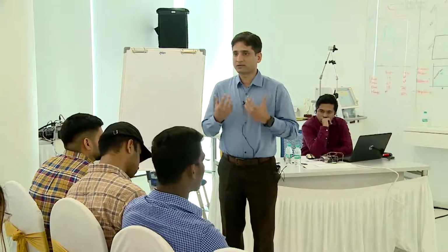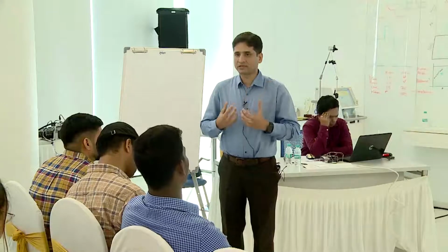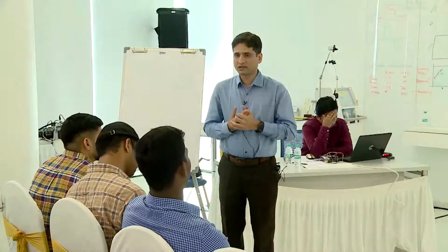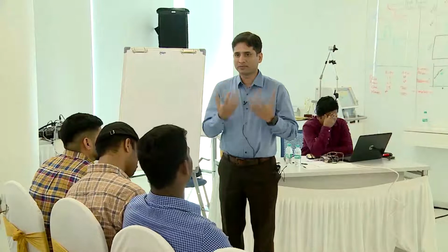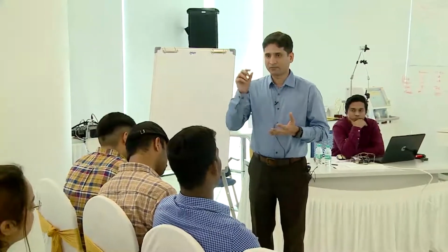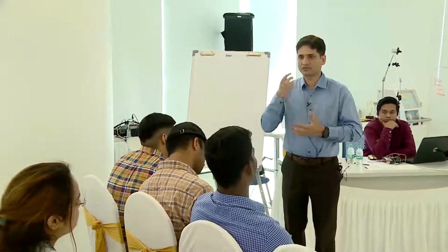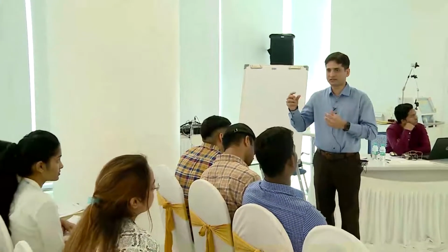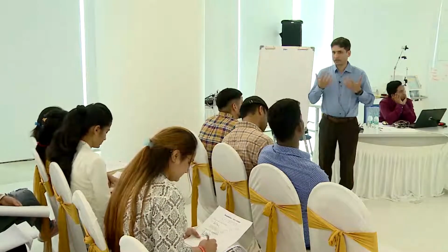Once the patient is taking a breath, how does the machine sense it? This is by either a pressure trigger or a flow trigger. But if the patient is completely paralyzed, then it is the time trigger. So the trigger can be a time trigger, pressure trigger, or flow trigger. Once there is a trigger on the machine, the patient will take a breath.